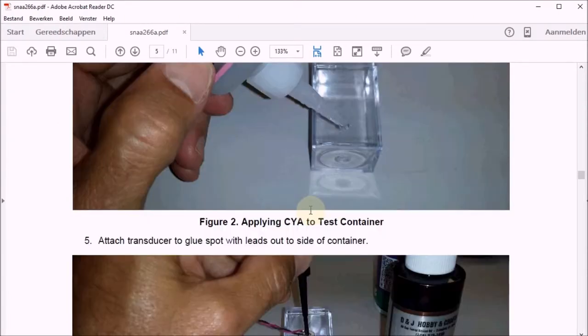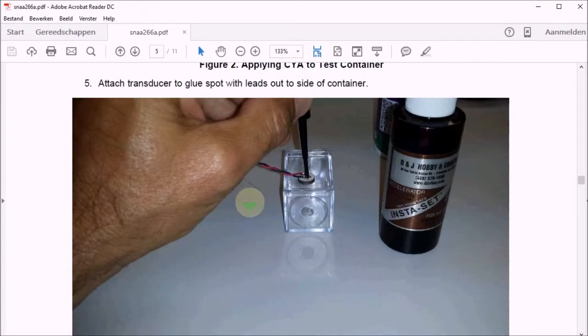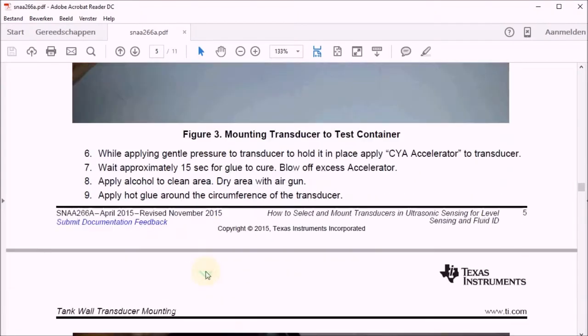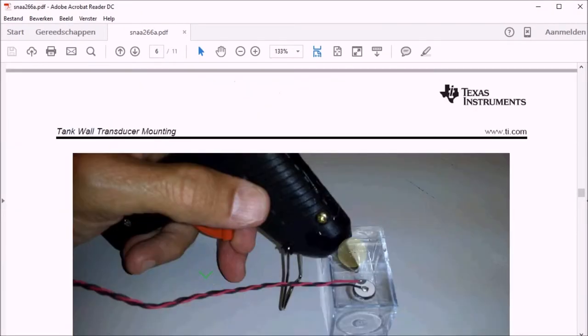Then once accelerator and glue are applied you have to put the transducer on and keep it in place for a good minute. Once the glue is dry you have to clean the area, then apply some alcohol again to clean everything, dry it and fill the whole thing with hot glue. So the purpose of the hot glue is to dampen and to get an enclosure.